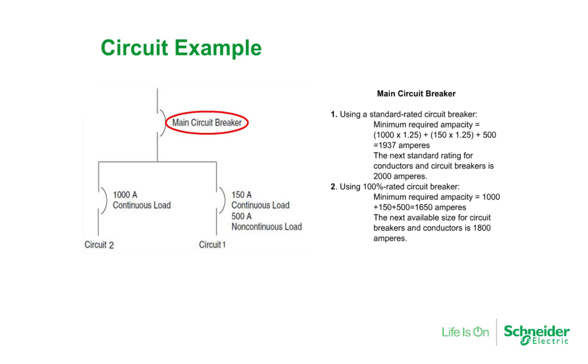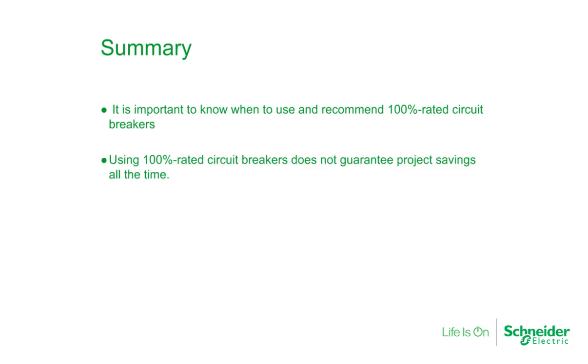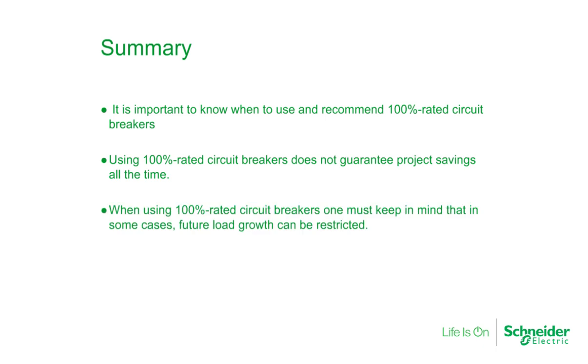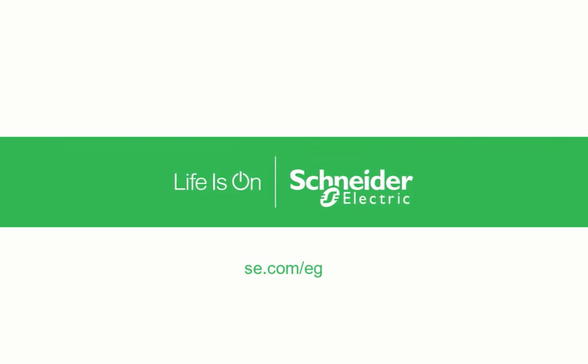In addition, the customer has the excess capacity of 150A for future load growth. To summarize, it is very important to know when to use and recommend 100% rated circuit breakers, as using them does not guarantee project savings all the time. In some cases, future load growth can be restricted. To use 100% rated circuit breakers, the entire system including the equipment must be listed for 100% operation.